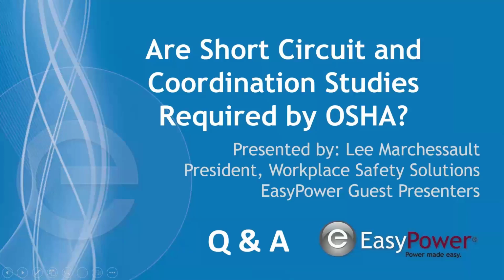Here's another question that comes up frequently. Does a safety switch, or do safety switches, required to have arc flash labels? Safety switches. I'm thinking a fuse disconnect or a disconnect for a motor. Yeah, so no, not necessarily. Generally, arc flash study is going to go down to the panel level. Personally, I prefer to do a study right down to the disconnect level if they are larger disconnects. 100 amp, maybe even 60 amp, but usually 100 amp, 200 amp, 300 amp, 400 amp switchgear disconnect switches should have labels.